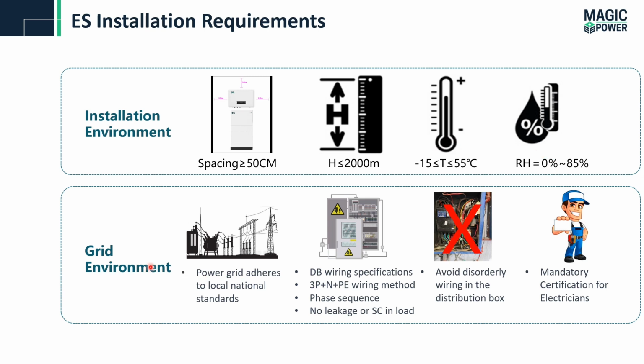If you talk about the grid environment, we should check the grid standard with the system, and the distribution box wiring in case of single or three phase. In case of three phase, we have to check the phase sequence, and there should be no leakage or short circuit on the load side, and we avoid disorderly wiring in the distribution box. And for installation, there must be a certified and professional technician or electrician for the system installation.